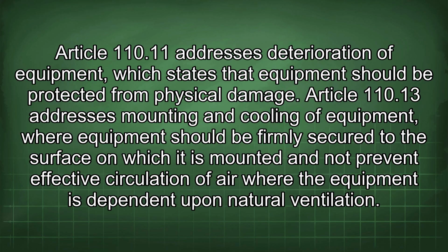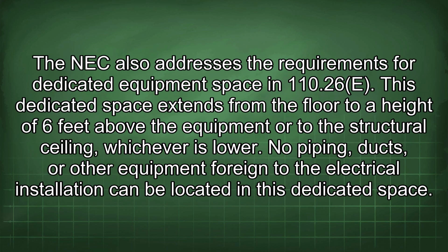Article 110.11 addresses deterioration of equipment, which states that equipment should be protected from physical damage. Article 110.13 addresses mounting and cooling of equipment, where equipment should be firmly secured to the surface on which it is mounted and not prevent effective circulation of air where the equipment is dependent upon natural ventilation. The NEC also addresses the requirements for dedicated equipment space in 110.26(E).